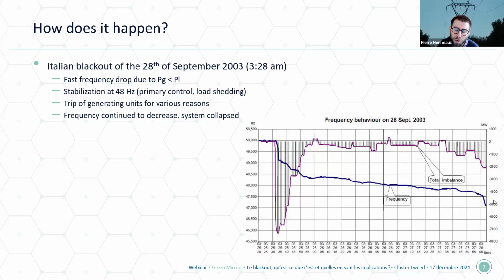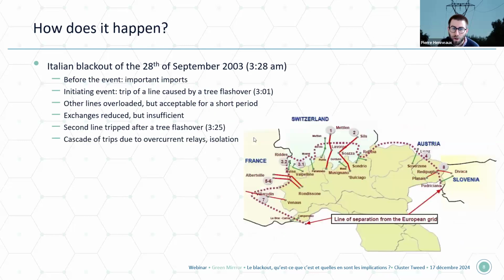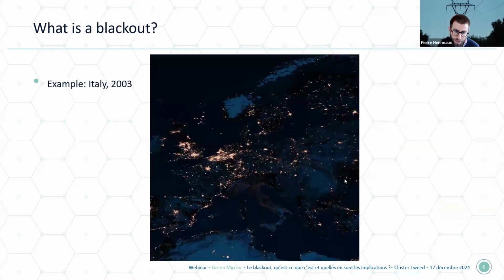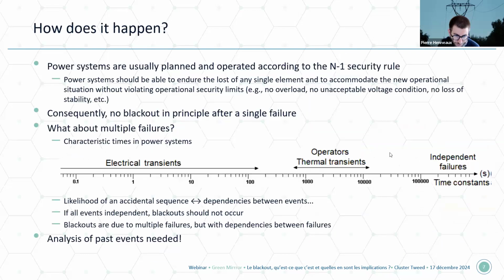And when you go below 47.5 Hertz, basically all generating units have the right to disconnect to avoid mechanical damage. Usually they need to be disconnected from the grid, and it's allowed by the grid code. So at that point, all generating units started to disconnect, and the system fully collapsed. So you had a total blackout, and that's why you can explain that Italy was in the dark.